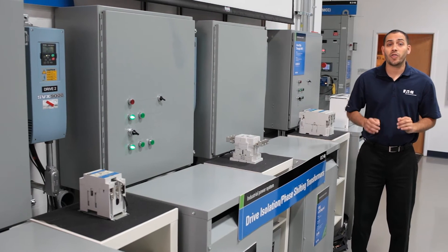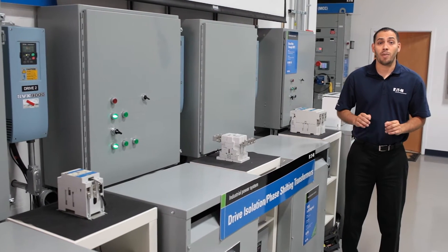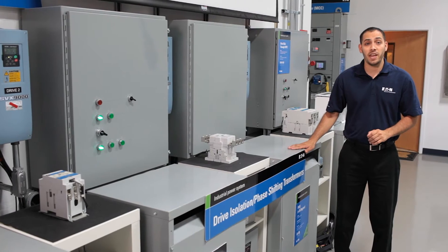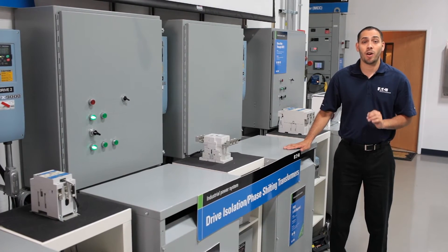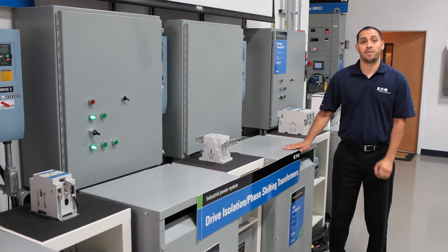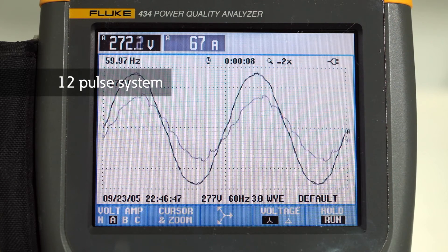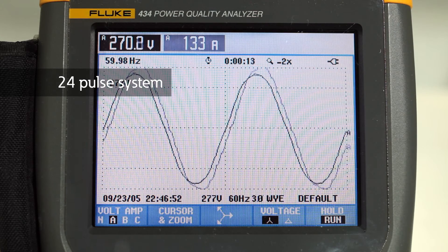Finally, a third solution is the use of special transformers. Harmonic mitigating transformers and phase shifting transformers can be used to cancel the harmonic currents. For example, phase shifting transformers can transition a system of six-pulse drives to reduce the harmonic distortion in the current and voltage.